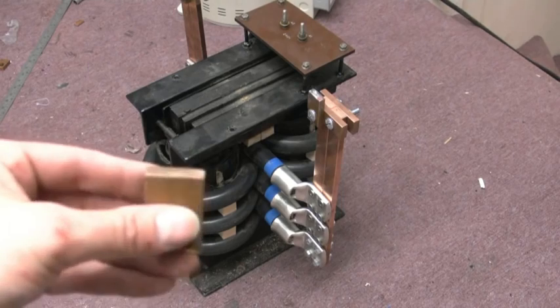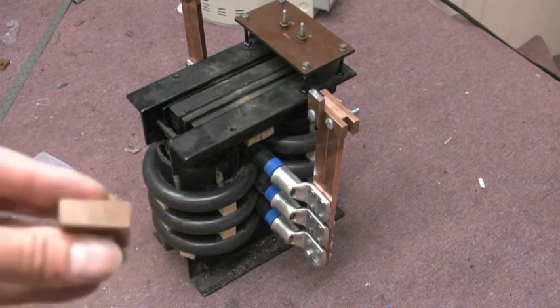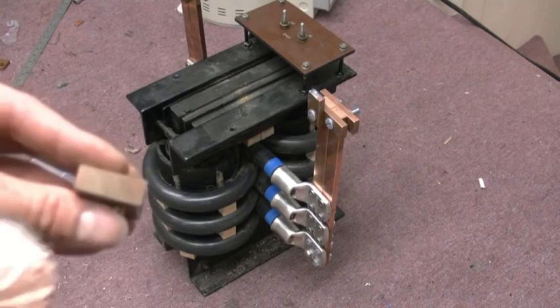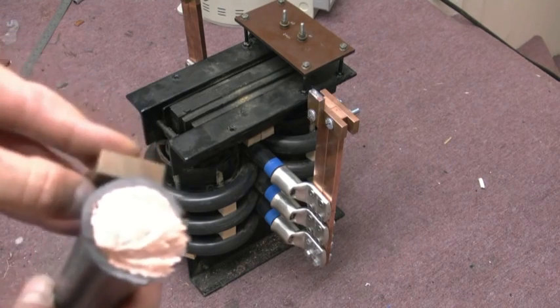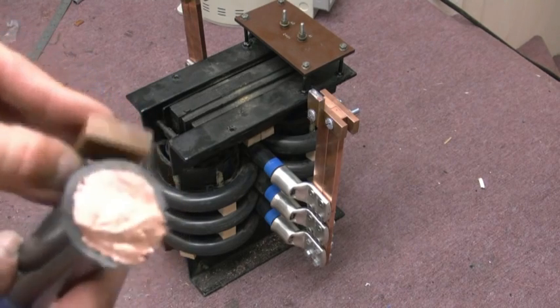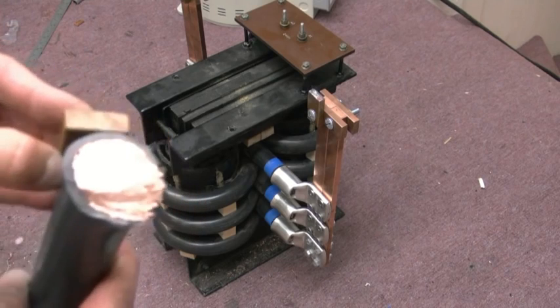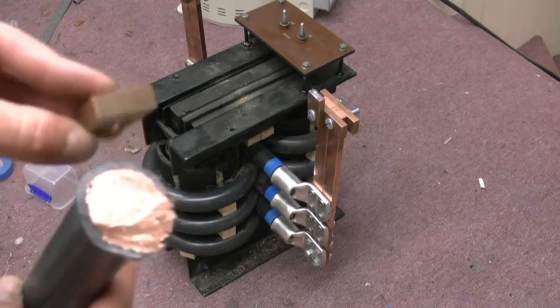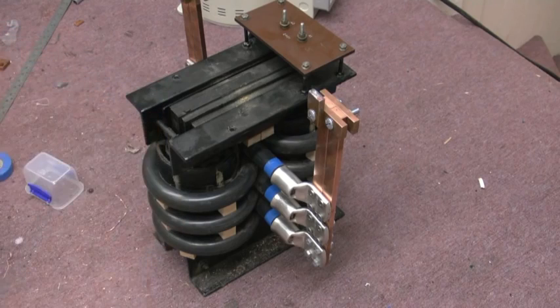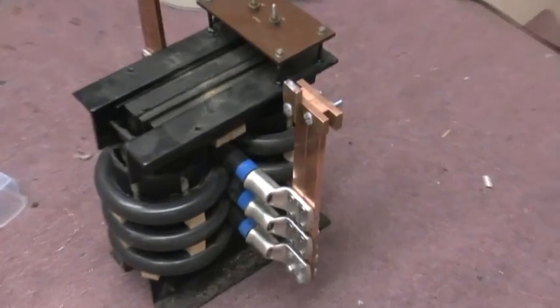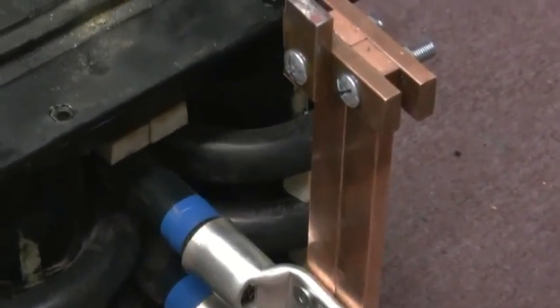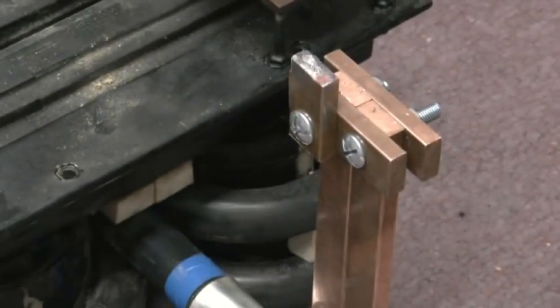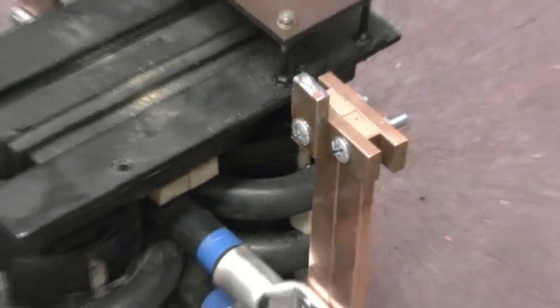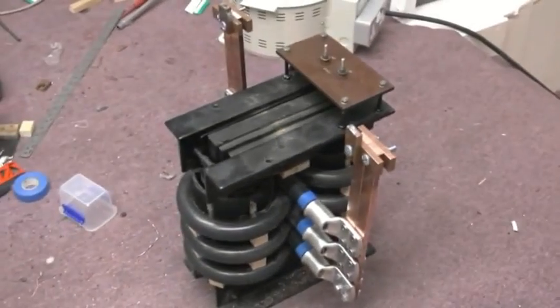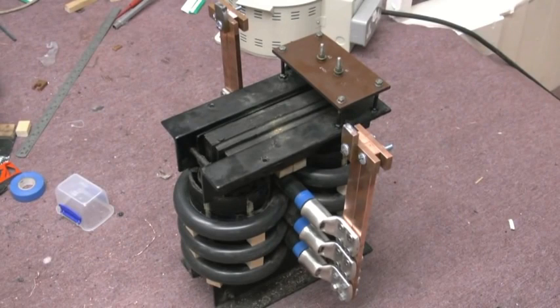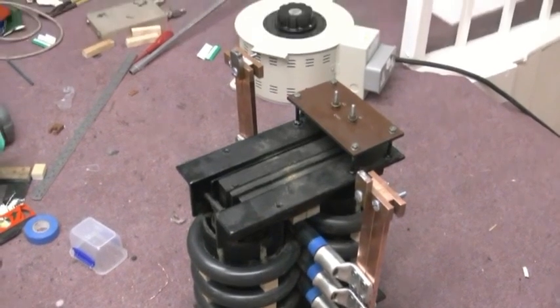That's the copper bus bar I'm using, the area of it, and that's the cable. So you can see that that cable obviously can handle a lot more than this bus bar. So I think I'm going to need some bigger bus bar if I want some serious amps. Probably 3" by 1" solid bar to handle that sort of output. But that's it, I think we're done with the high current transformer now.